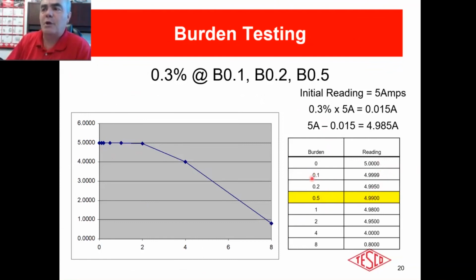In this particular case, this transformer that we were working on, its faceplate said 0.3 at a burden of 0.1, 0.2, and 0.5. All right. After that, its accuracy is going to deteriorate. The manufacturer doesn't necessarily tell you how it will deteriorate, certainly not on the faceplate, but you can get these graphs from the manufacturer, and you can get this data from the manufacturer. Remember I said it's 0.3% right there.